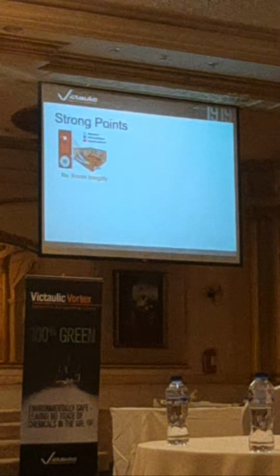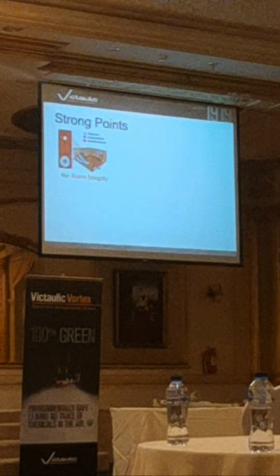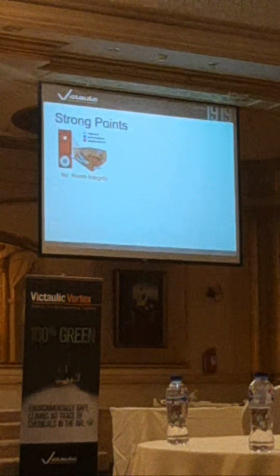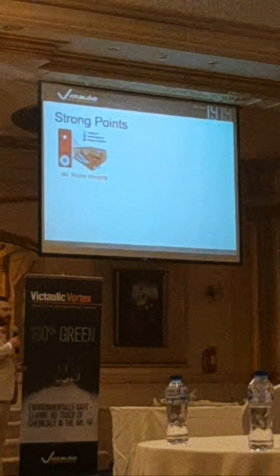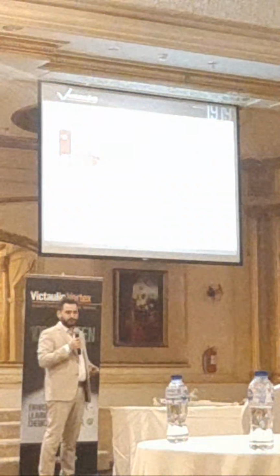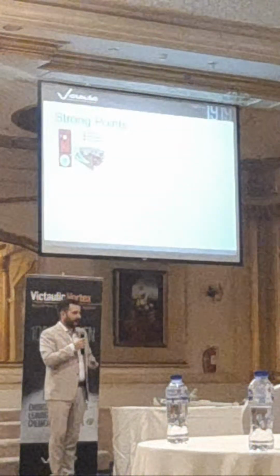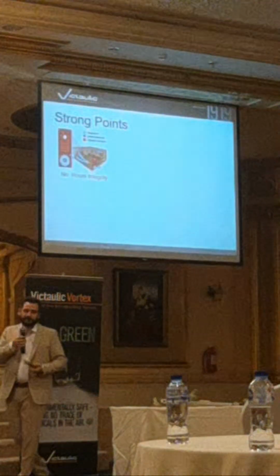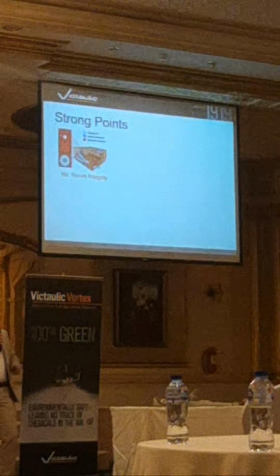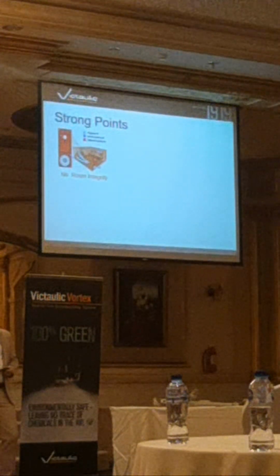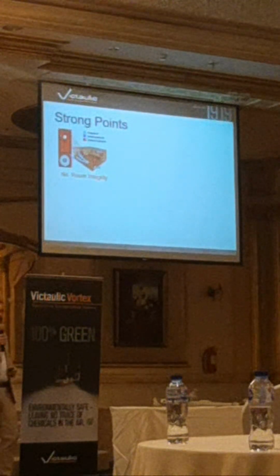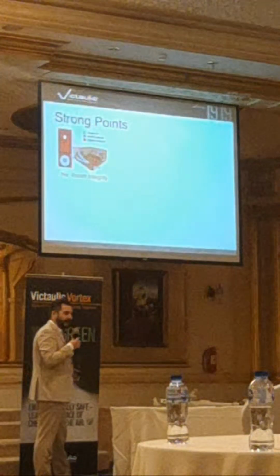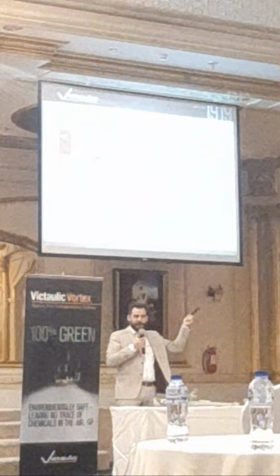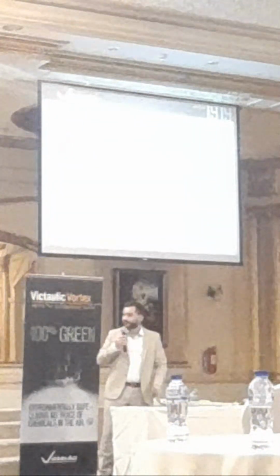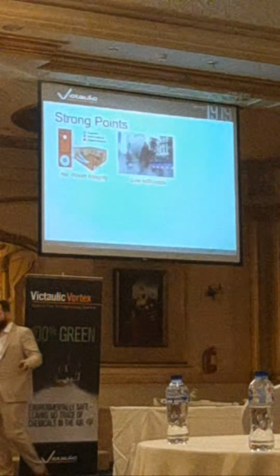The strong points that we have with the Vortex system, or a hybrid system. The first one is room integrity, which I mentioned multiple times throughout this presentation. Compared to a gas system, we do not require a completely sealed room, so you don't need to install pressure relief dampers. Because of that, you're saving a lot of maintenance costs, and you don't have to worry if another contractor that isn't a fire contractor comes in - am I still going to have a safe system? At the end of the day, if a fire breaks out and the gas system does not work, who are they going to contact? Not the contractor that made that permanent opening, but the contractor that installed the system. So that's something to always think about, and the Vortex system takes that all the way.